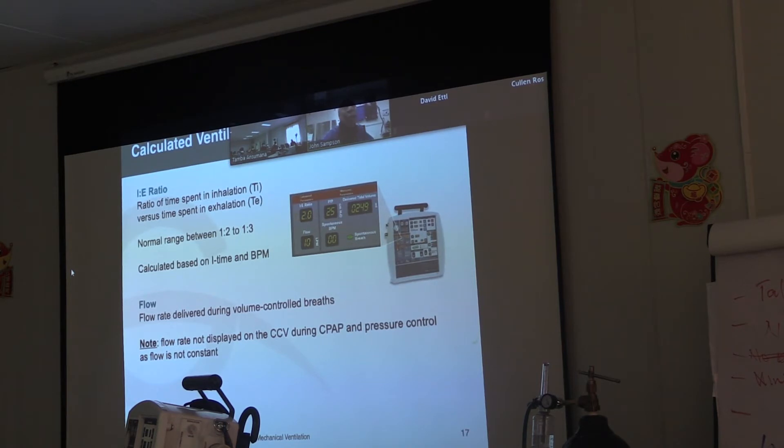I to E ratio, which we mentioned before briefly, is the ratio of the inspiratory time to the expiratory time. A normal I to E ratio would be one to two to one to three. So for every one second of inspiration, you might have two seconds or even three seconds of expiration. On this ventilator, you manipulate the I to E ratio by changing the inspiratory time, the I time.